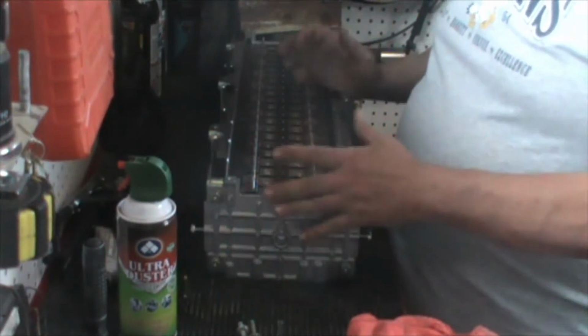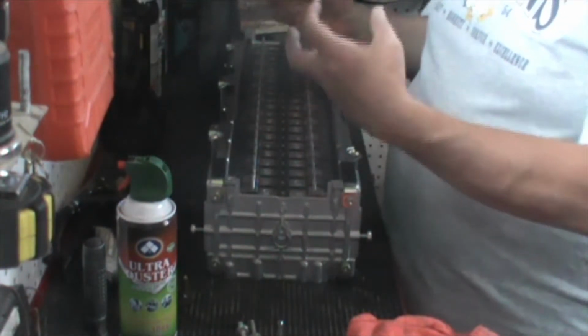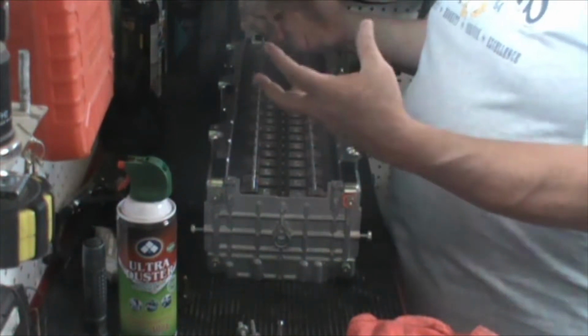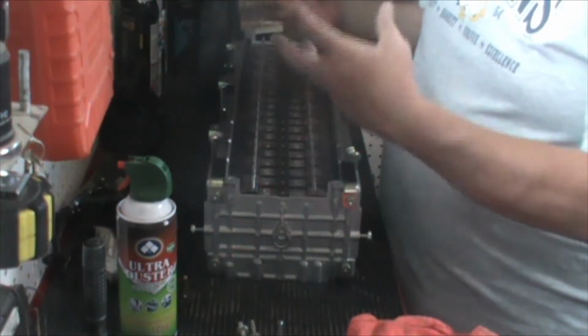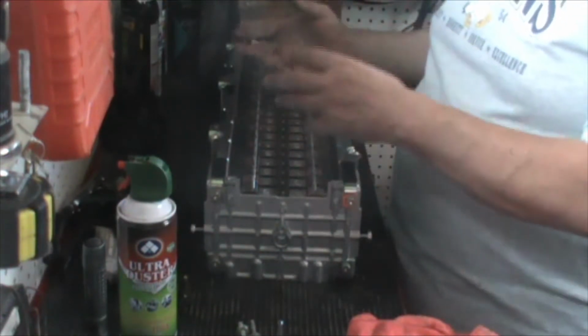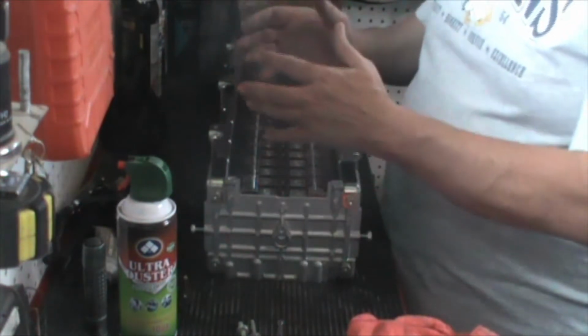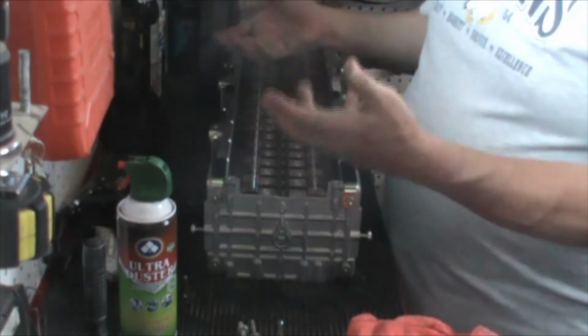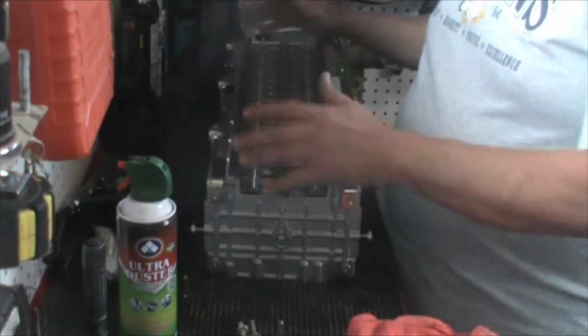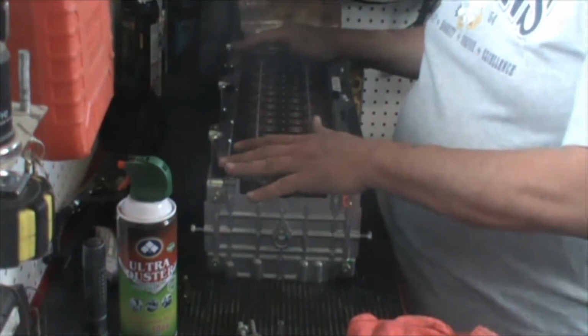As a battery charges and discharges, there's a small amount of heat generated. The faster the charging or discharging, the more heat that's generated. This translates into thermal energy. And as Einstein said, energy cannot be created or destroyed, it can only be changed from one form to another. So with this heat comes expansion and contraction, which is a form of mechanical energy. Battery developers use compression bars to manage this mechanical energy, and all batteries are subject to the phenomenon.